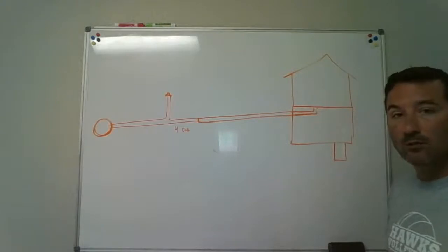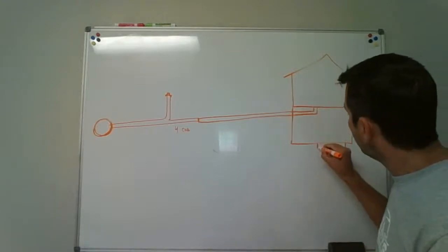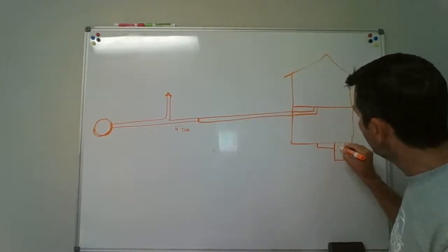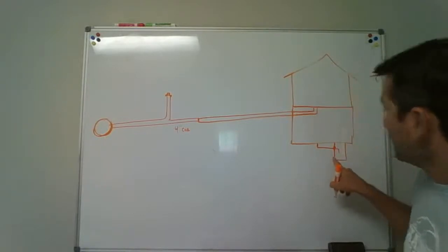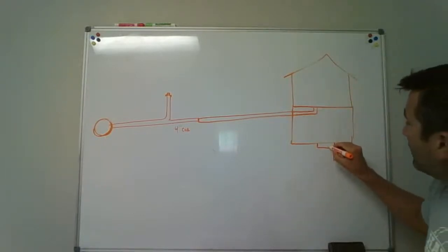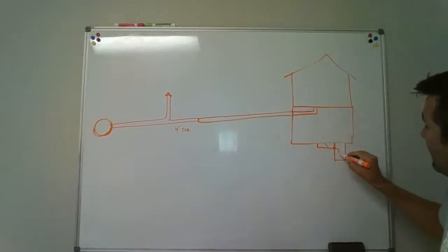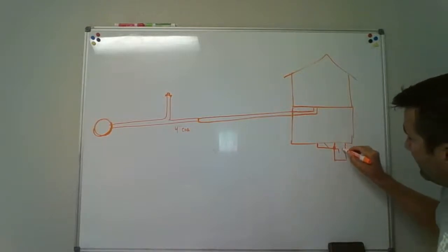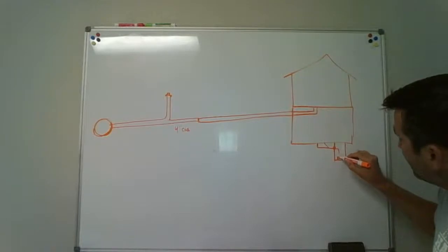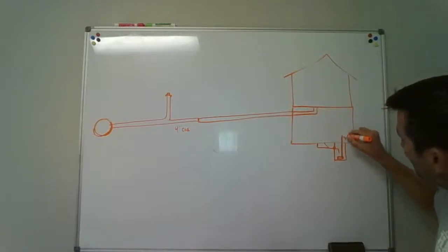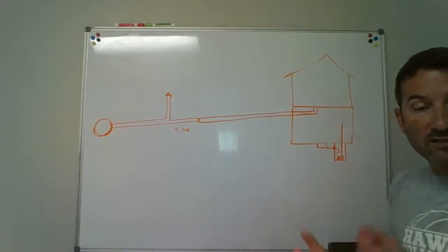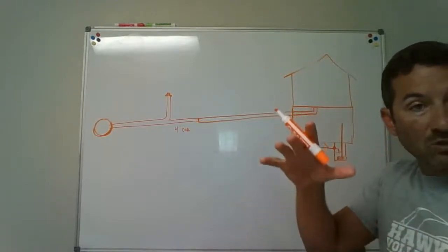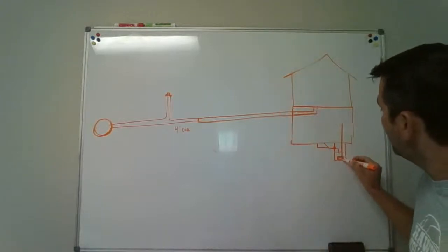Going to stick that in the ground, and then I'm going to drain everything, and it's going to flow into the side of this can. It's got an opening there. This drains in and it flows into here. So I've caught all the plumbing to this bathroom. It drains into this tank, and then there's a pump down in here, and it's got a float switch on it. Okay, so when the water level gets high enough and all that sewage starts to fill that tank, the float switch comes on and activates, and the pump kicks on.